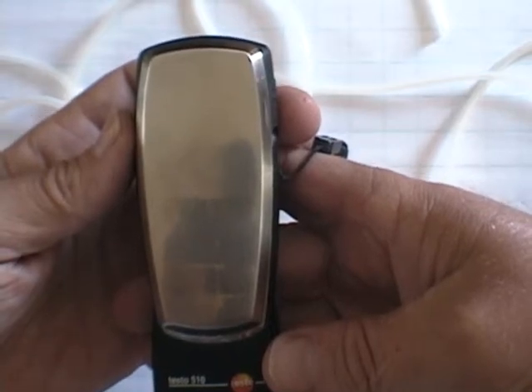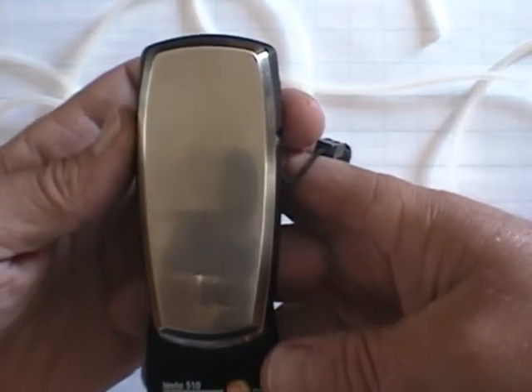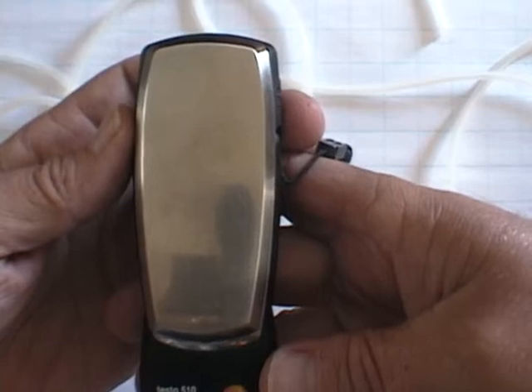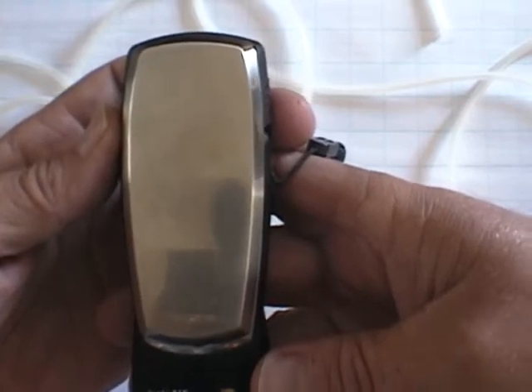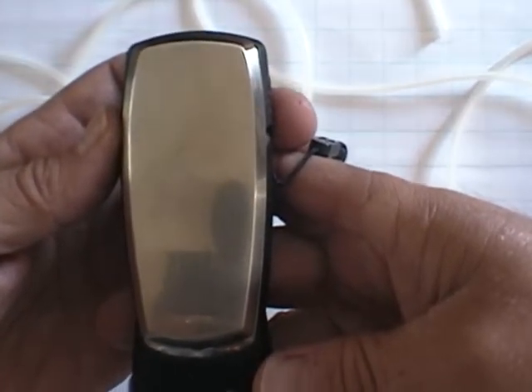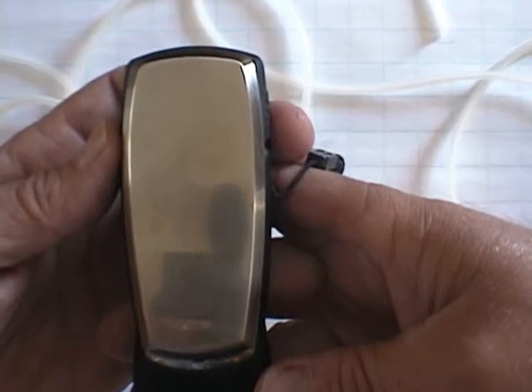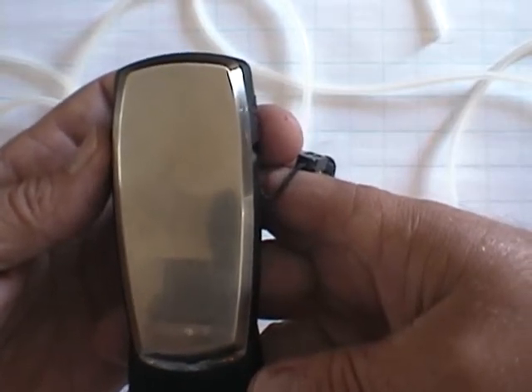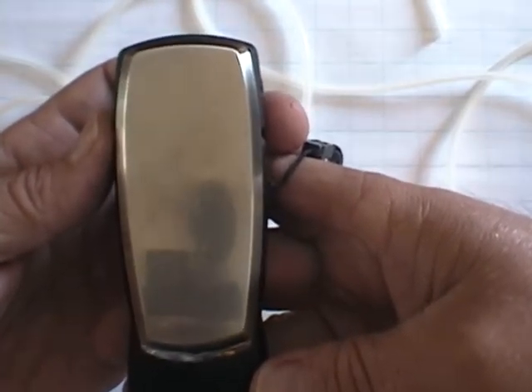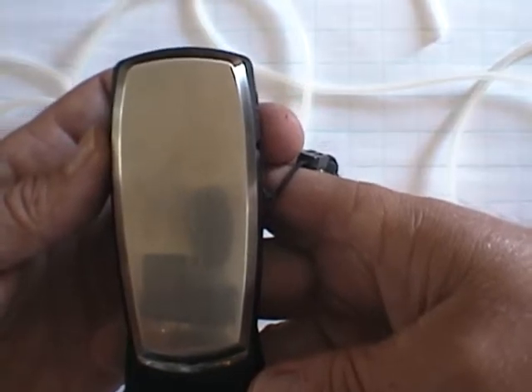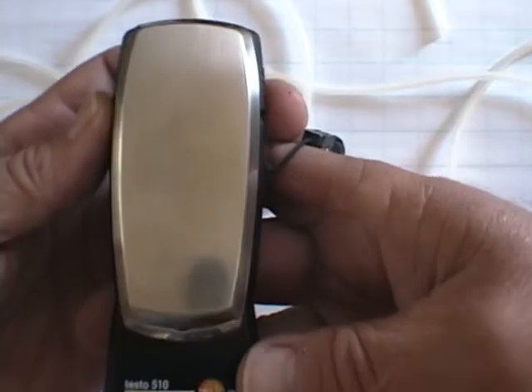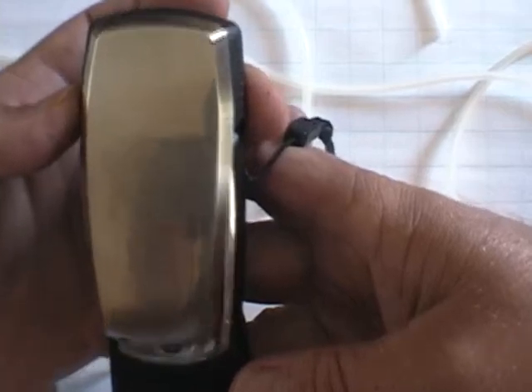locate any airflow problems we have in an air conditioning system. If we get an indication of low or high airflow as a result of measuring the cubic feet per minute, CFM, for the system, then this is a very handy tool to locate where we need further investigation to expose what the problem is. You just simply remove the cover.